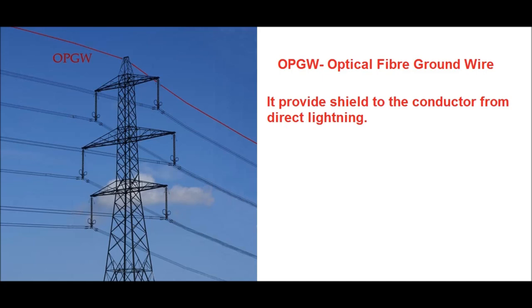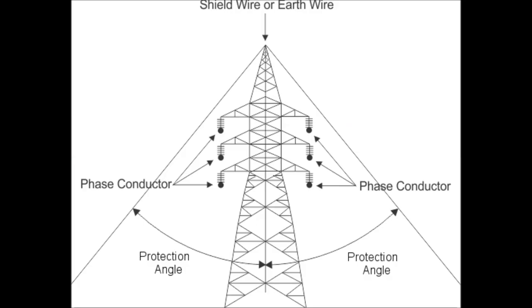A diagram has been shown for a 132 kV double circuit line. Here the earth wire is located at the top of the tower and it provides a protection angle, or shielding angle, to the phase conductors as shown in this diagram. Since the earth wire provides a shield to the phase conductors, it is sometimes called a shield wire.